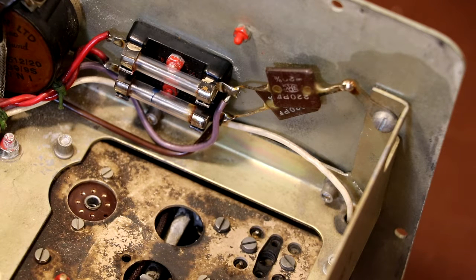Now Y-rated capacitors are designed to be installed between the live conductor and the earth. But quite often for these modern capacitors you can buy what they call XY rated, and that's what I recommend that you look for. They're designed to be connected either across the mains or between the live conductor and ground. Don't just use any old capacitor, because they could go short circuit, and if they do, they're going to blow a fuse, or even worse, they could start a fire. So it's important that when you're connecting capacitors across the mains, you use the right type.